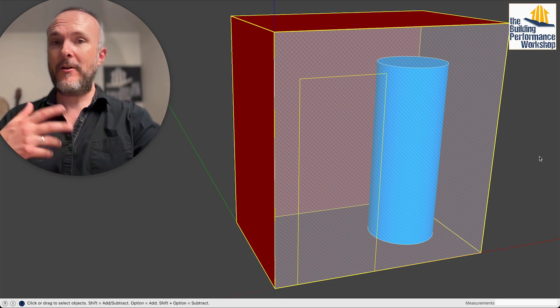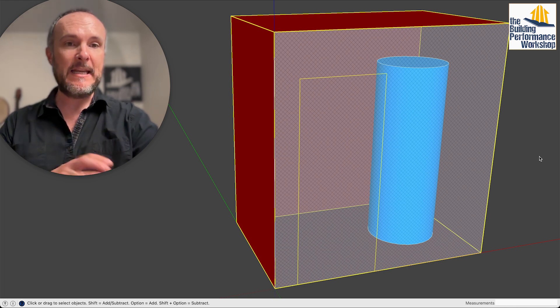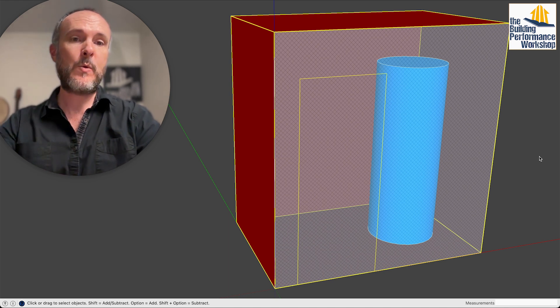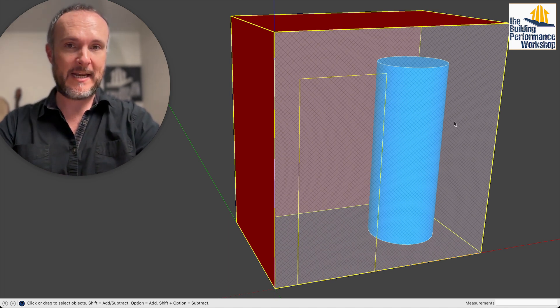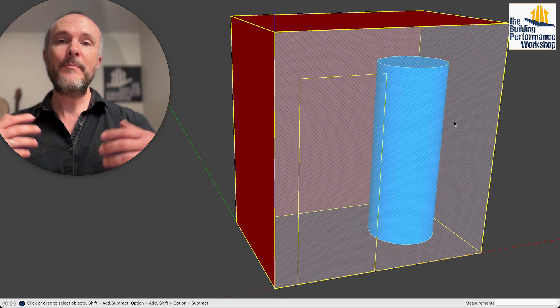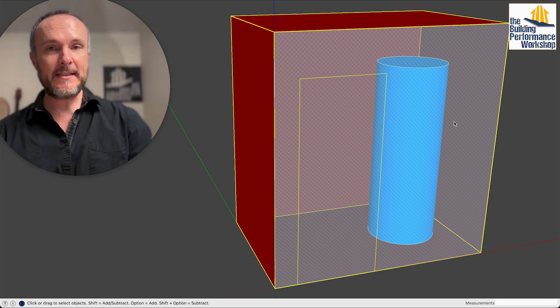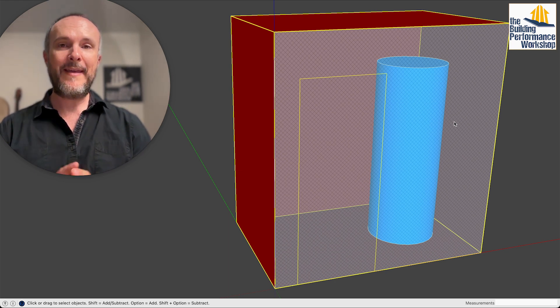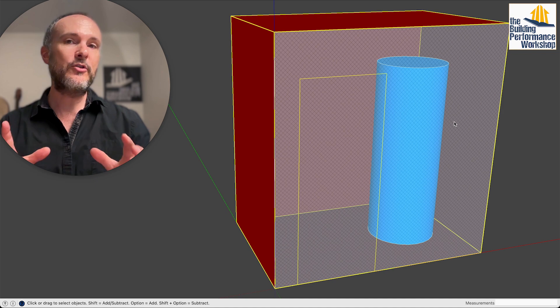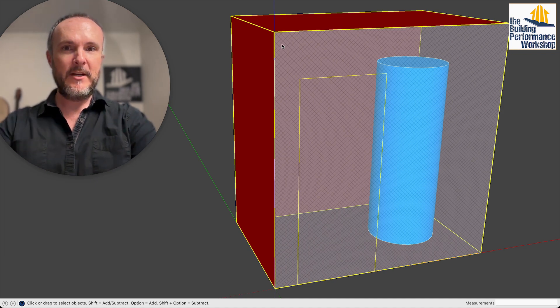One of the things about following the directions from the manufacturer is most of them are going to require that you put it in a room that is the proper size. They require that this device be put into a room that has 700 cubic feet of air.